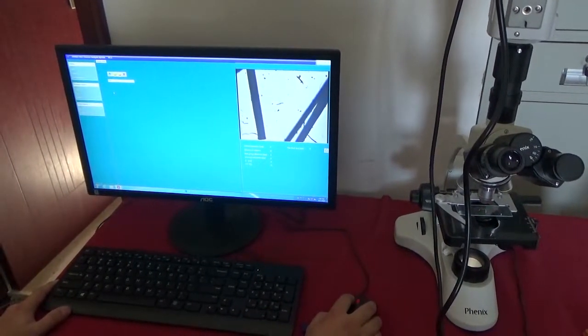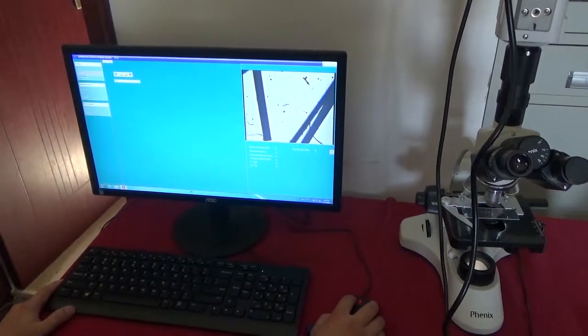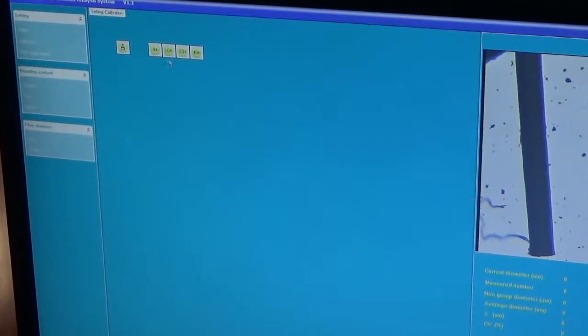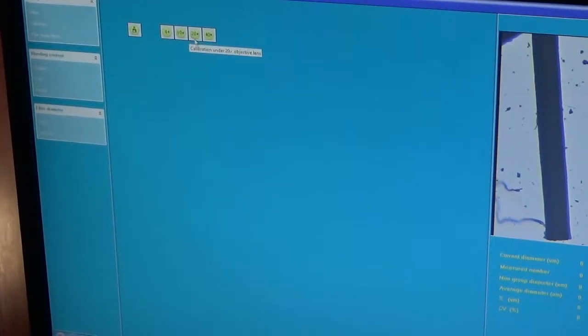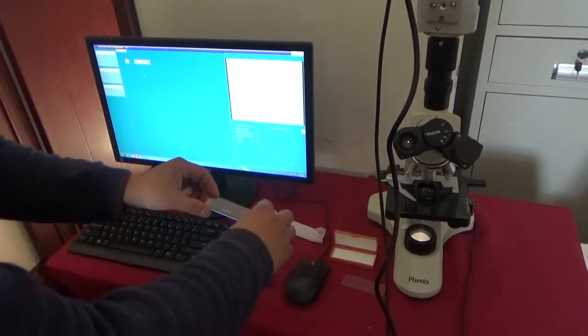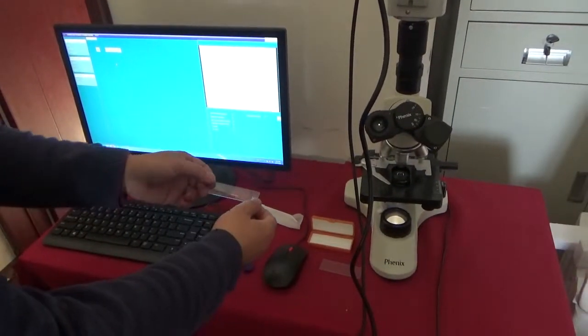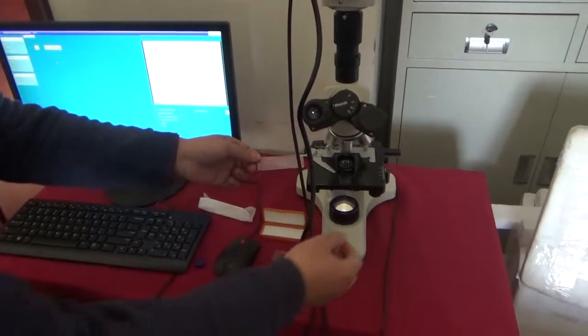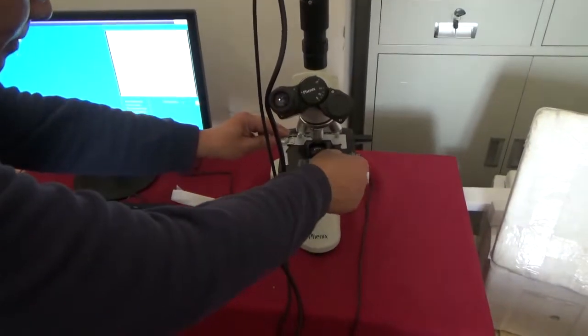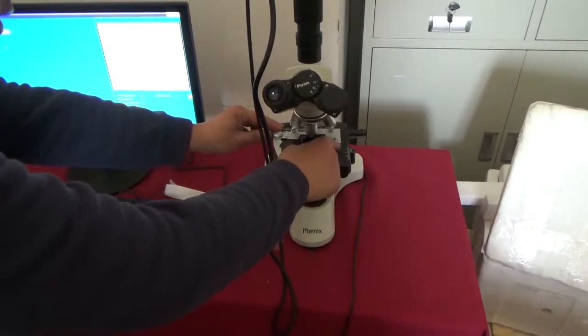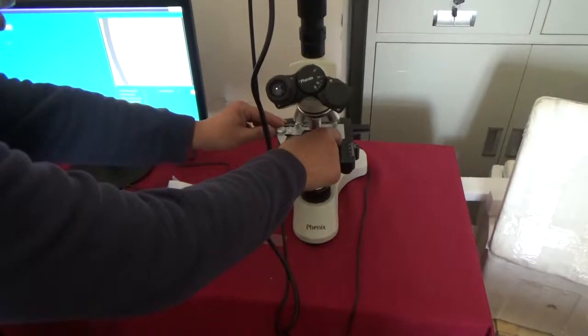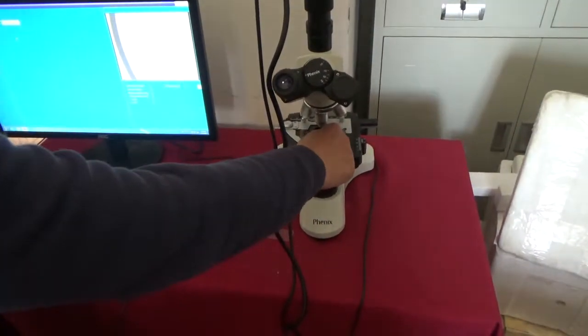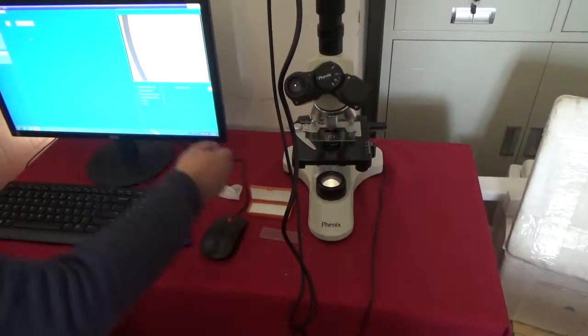Now we carry out the calibration. Click this one, and this magnification, you can see there are 4 magnifications here: 4, 10, 20, 40. Place the standard scale onto the stage. There is a 1 millimeter scale on the glass plate. You can see it on the picture.